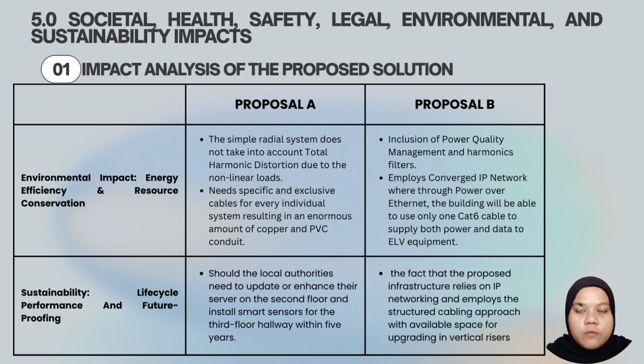The next one, point 4, environmental impact, which is energy efficiency and resource conservation. For Proposal A, the simple radial system does not take into account total harmonic distortion due to the nonlinear loads and needs specific and exclusive cables for every individual system, resulting in an enormous amount of copper and PVC conduit. For Proposal B, energy efficiency and resource conservation include power quality management and harmonic filters. It also employs a converged IP network through Power over Ethernet. The building will be able to use only one Cat6 cable to supply both power and data to ELV equipment.